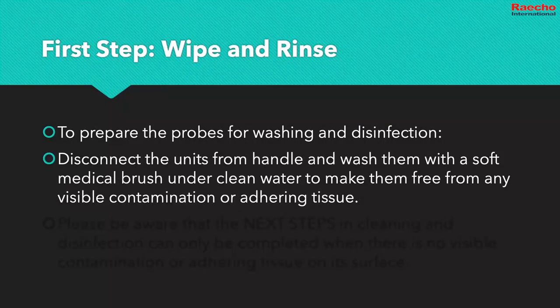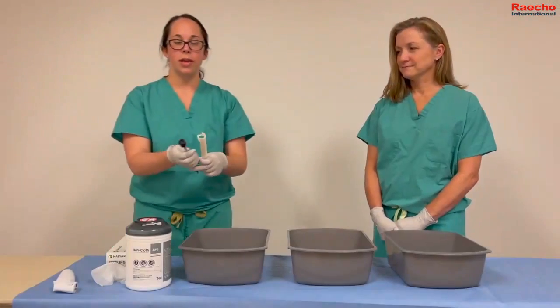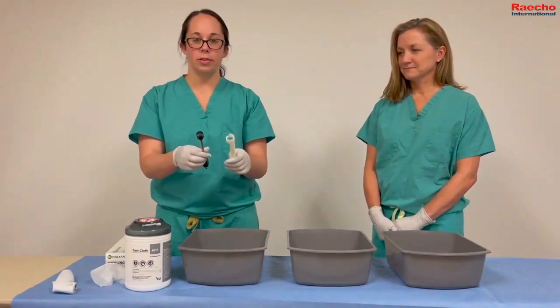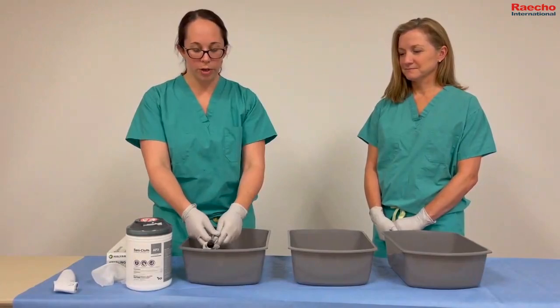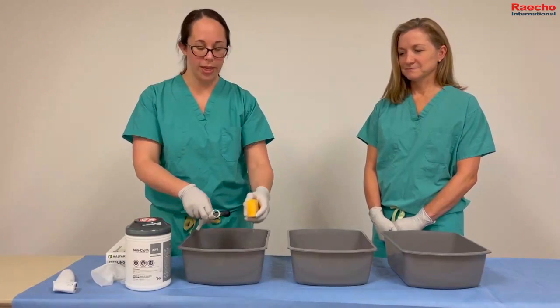Disconnect the units from the handle and wash them with a soft medical brush under clean water to make sure that they are free from any visible contamination or adhering tissue. You must use a very soft brush for this step, otherwise there is a risk of damaging the probe tip.